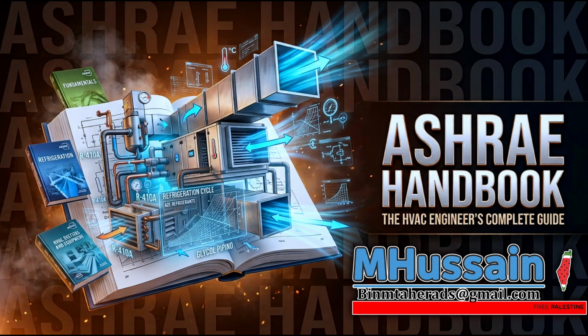So how does a steam trap solve a high-speed liquid battering ram? A steam trap is essentially a mechanical valve designed to differentiate between gas and liquid. It selectively allows the liquid condensate to drain out of the high-pressure pipe while trapping the steam inside so it can keep doing its job. What the committee did in the 2024 equipment volume was update the mathematical safety factors for sizing these traps.